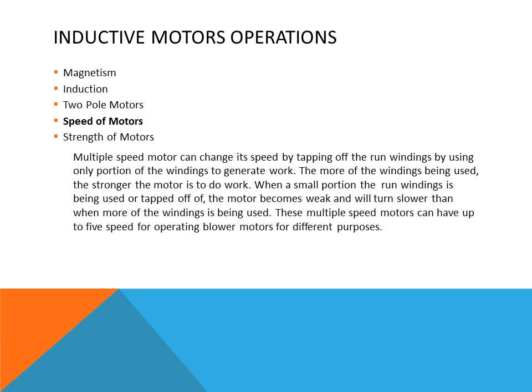Multiple speed motors can change speeds by tapping off portions of the run windings. Using only a portion of the windings generates less work, making the motor weaker and slower. When more windings are used, the motor is stronger. These multiple speed motors can have up to five speeds for different purposes. Most residential furnaces use a split phase motor that is also a multiple speed motor, with speeds to control different volumes of air for air conditioning and heating.